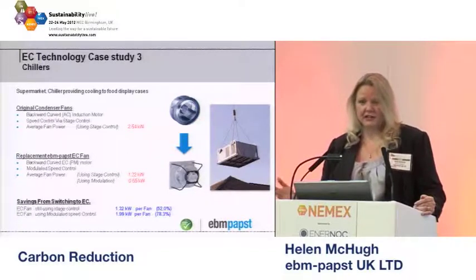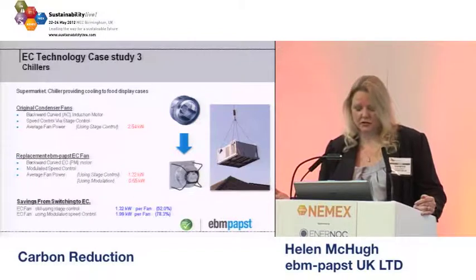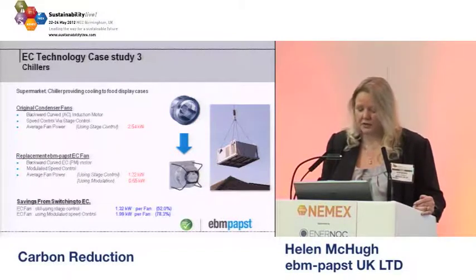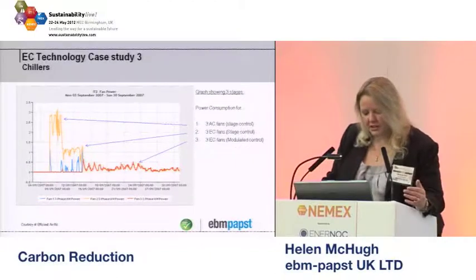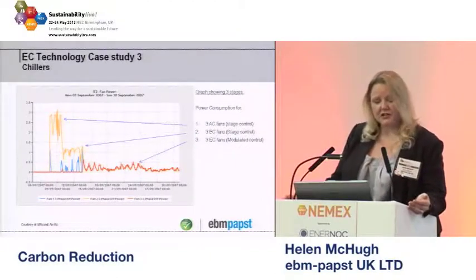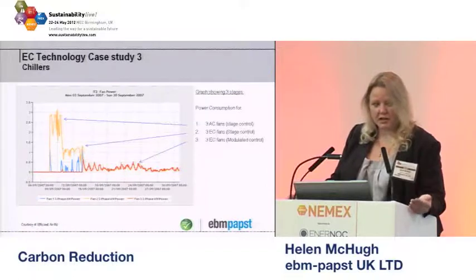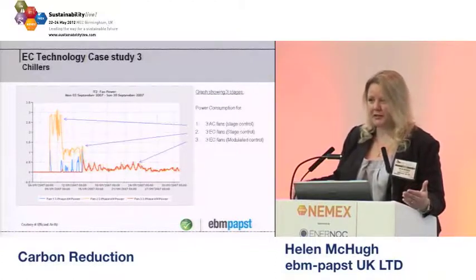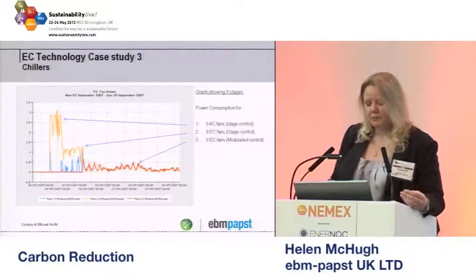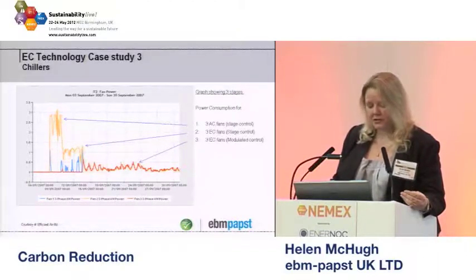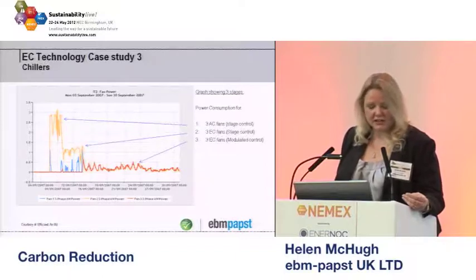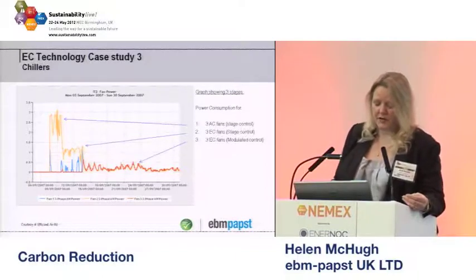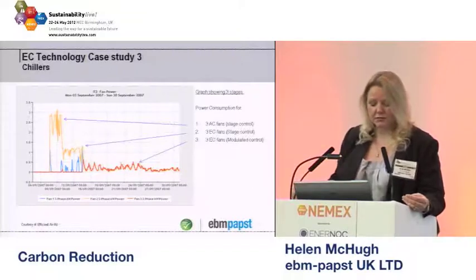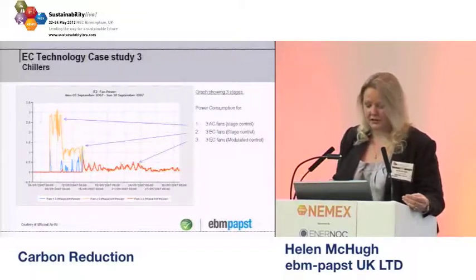But in addition to that, then they looked at changing their speed control function. And it's easier to see if we look at a graph of the performance. So on their chiller, they had 3 fans. And you'll see on that graph there, you've got a yellow, a blue, and a red line. And they represent the individual fans. So normally they would have what they call stage control. So they have one fan on all the time, then they'll bring in another and another. Now you'll see there's 3 points on that graph. Firstly, we swapped out for the EC fans, and you'll see the drop there for around about 50%. And we're still running in the same format, one fan, then another and another.